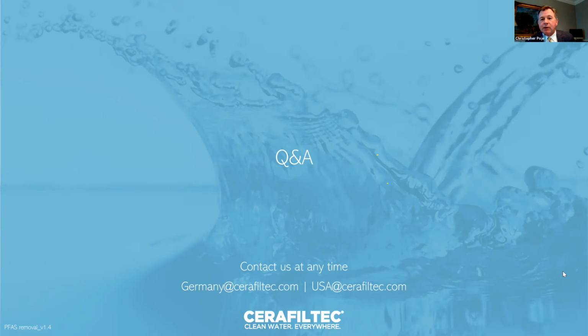The flux rate is kind of like the question of how long a ladder do I need? And my next question for you would be, well, what are you trying to do with the ladder? So it depends a lot on the contaminants in the water, the temperature of the water, the other conditions, what kind of pre-treatment is available or needed, and we can adjust from there. In an MBR setting, we'll be as low as 40 LMH in replacing polymeric membranes where there's good pre-treatment already. We've got several designs at 700 and 750 LMH. So that's 441 GFD effectively at the top end for a good drinking water application.